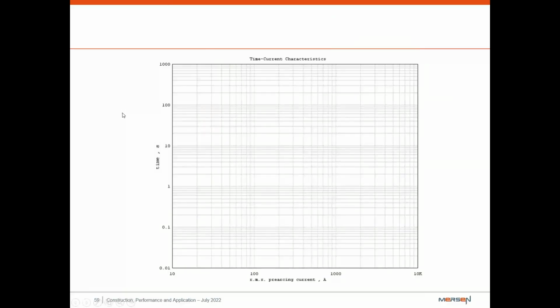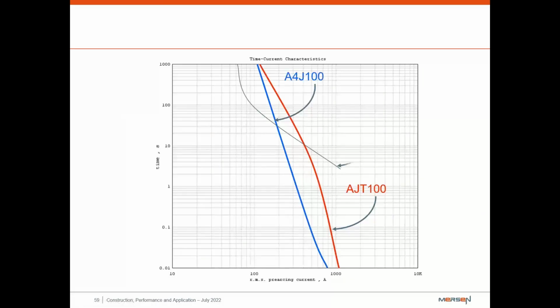Taking a look at the time current curves for this, we're going to have the AJT100 and the A4J100 with a NEMA class 20 overload relay. With the overload relay, say you have your start coming in, and you can see right here at the A4J, these are all going to be sized at 150%, which is inside the maximum of 300%. You can see that the A4J is going to clearly open upon start, and we can't have that because this is going to be normal operation. There's not going to be any kind of an issue.